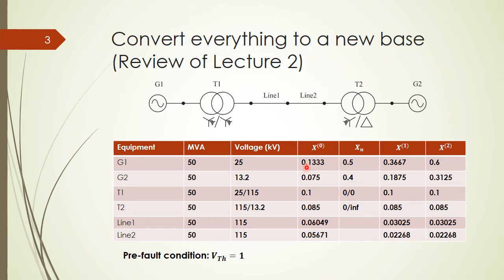The zero sequence impedance is given, and together with it we have the connection between the neutral and the ground, with values for Z2 and for transformer 1 and transformer 2. For transformer 1, the Y-to-Y configuration has the neutral connected to ground, so the zero sequence short circuit between neutral and ground is zero for both primary and secondary sides. For transformer 2, only the primary side has the neutral-to-ground connection; the secondary side is delta, so it is not connected to ground, and therefore the reactance there is infinity.